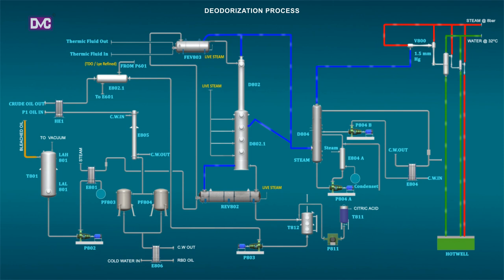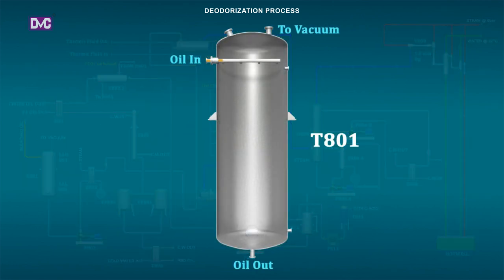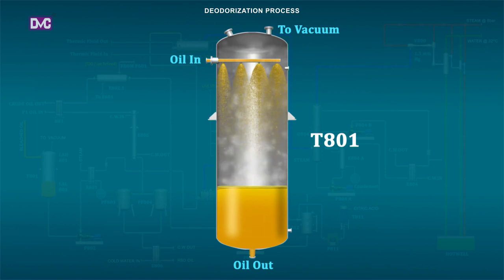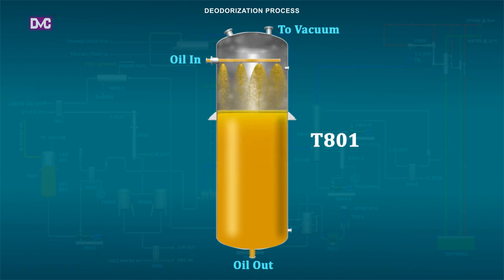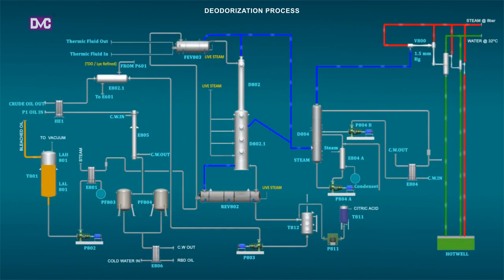Deaeration. The tank T801 is kept under the vacuum. It acts as a buffer for the incoming bleached oil as well as a deaerator to remove dissolved air. The combined buffer and deaerator avoids double conveying of the oil during the process. The level in the tank can be monitored by level indication by PLC operation.